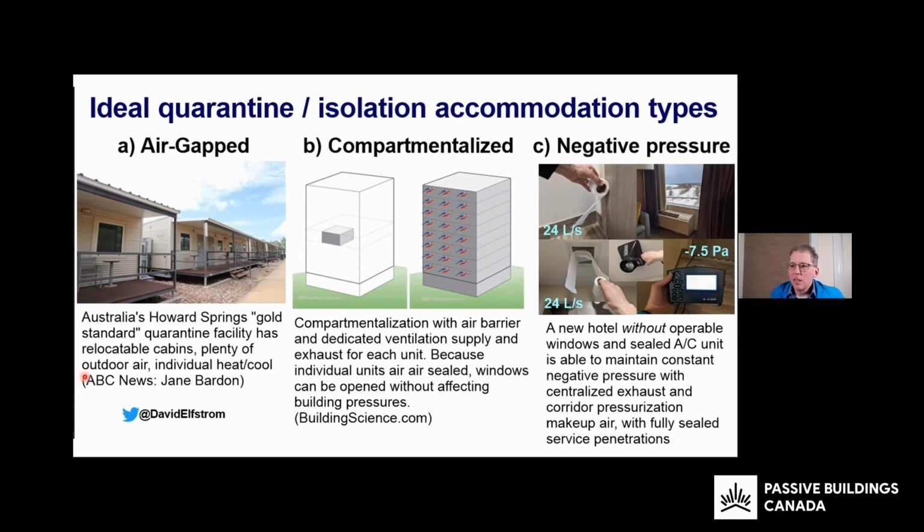So that works out to like a fallow time at a dentistry between patients. They say you have to have 3 air changes. Doesn't matter if it's per hour, you have to wait an hour if you have 3 air changes per hour. So the idea is to increase the effective air changes with filtration or ventilation, and you can reduce the contaminant levels much faster. It always takes extra time to dilute; there's always some little bit left until you get, I guess, to homeopathic levels of contaminants.